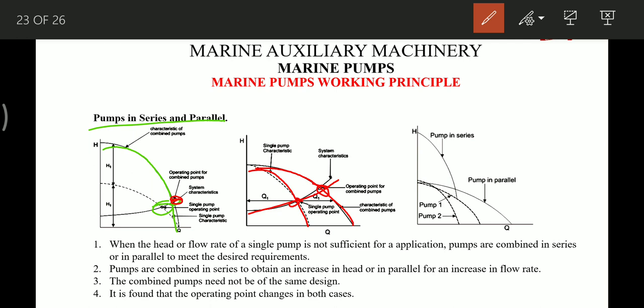When the two pumps are not identical, there are separate combined curves for series and parallel operation. Pumps are combined in series to obtain an increase in head, or in parallel for an increase in flow rate. The combined pumps need not be of the same design. The operating point changes in both cases.